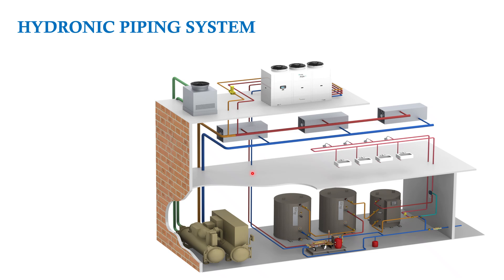In any typical air conditioning plant, a four-pipe system has a hot water generator and a chiller to satisfy both heating and cooling requirements for any season. At the application level, there are air handling units connected to both chilled water and hot water piping. There is also a cooling tower rejecting heat for a water-cooled chiller, and a cascade taking care of the hot water side.